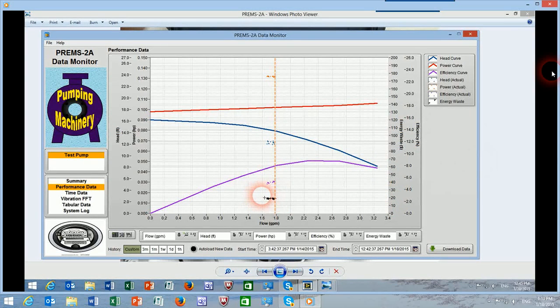So the pump is running in a way that the deficiency between actual efficiency and projected efficiency translates to $20 wasted a year. It's a very small pump, obviously, so the number is small, but it could be $20,000 or $2 million, depending on the size of the pump. Well, how does this data get calculated? Part of the input to the program is utilization of the pump, 7 days a week, 365 days a year, or 20% of time, 30% of time. Energy cost, 10 cents per kilowatt hour, or whatever other cost your particular plant might be incurring.